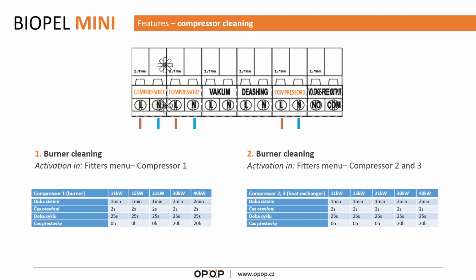Cleaning is set from the factory to clean only when the boiler is switched off. So basically the boiler is heating, and when the temperature of the boiler or the temperature inside the room is reached, the boiler is switched off, and then during the extinguish phase of the boiler the compressor will be activated and will clean step by step the burner and the heat exchanger.